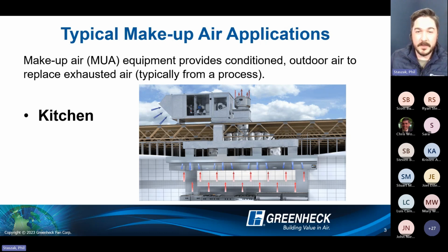The reverse scenario: if that door is suctioned closed and you have to tug on it a little bit to get it cracked open, then you feel that rush of air as you open the door. Probably the better scenario, because at least you're getting all of that kitchen grease-laden exhaust air out of your space, but you've got an extreme negative in that space. So every nook and cranny, that's the purpose of makeup air. It's really just to balance out that airstream.